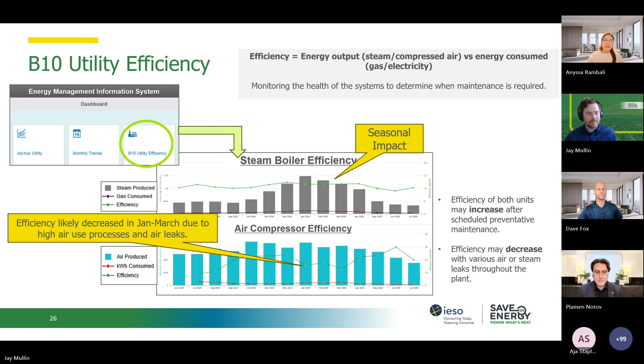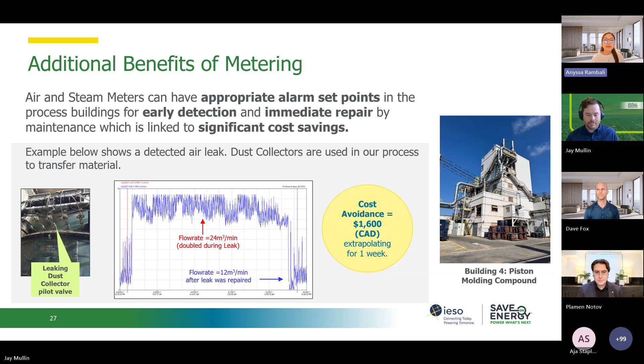Lastly, I just wanted to show the benefits of metering. The air and steam meters can have appropriate alarm set points. This shows an actual leak that occurred in our process, a dust collector pilot valve. The flow rate was 12 meters cubed per minute, it doubled to 24, and then after it was repaired it went back to 12. Say that leak was undetected for a week, it could cost us up to $1,600 Canadian. So just the benefits of metering for early detection, you can have appropriate alarm limits.